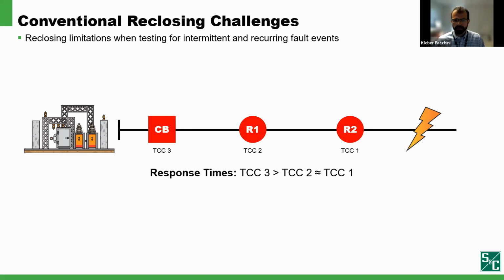Fault happens, R1 and R2 will trip to clear the fault. And why is that? As explained, both devices are configured with the same TCC curve, so they will both trip. R1 will start the reclosing sequence. No fault is detected and it remains closed. Detecting presence of voltage, R2 will start its reclosing sequence. And detecting no fault, R2 will remain closed as well.